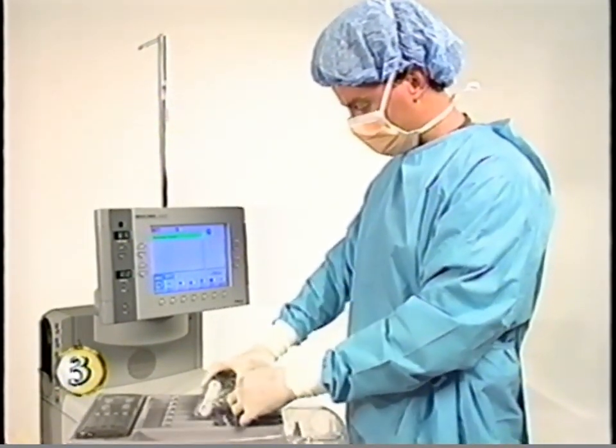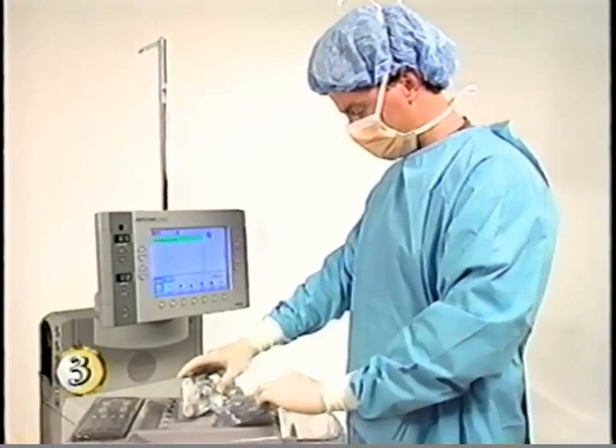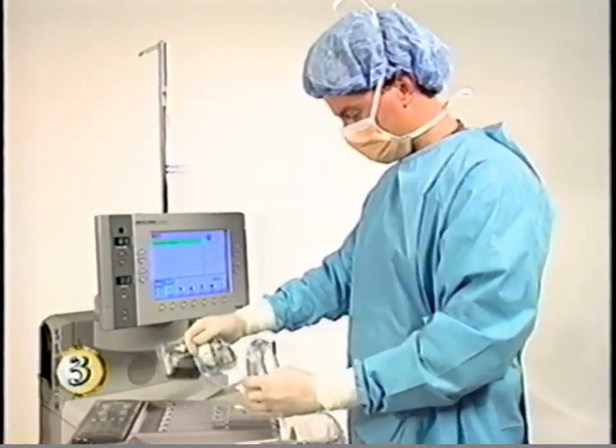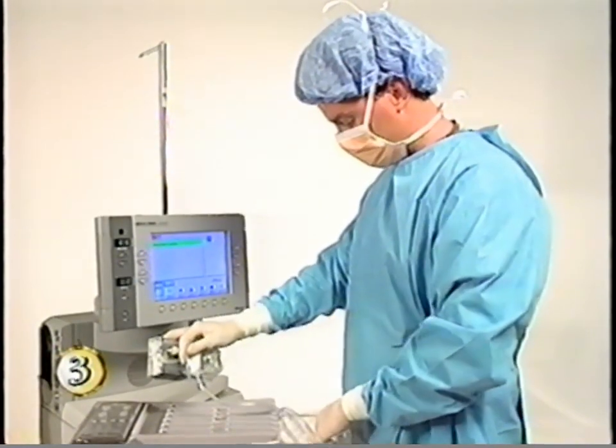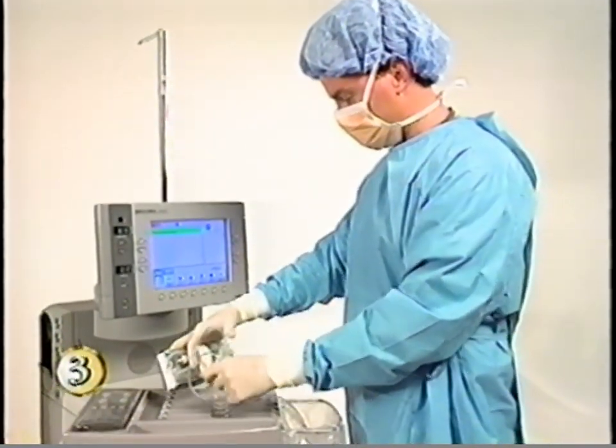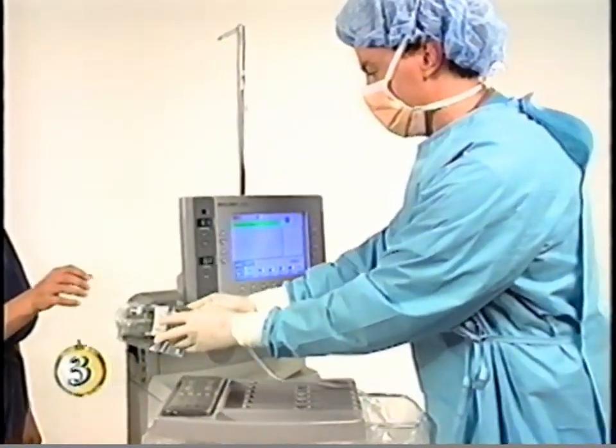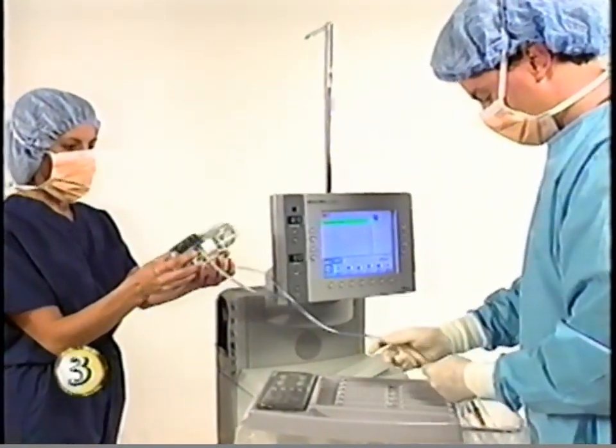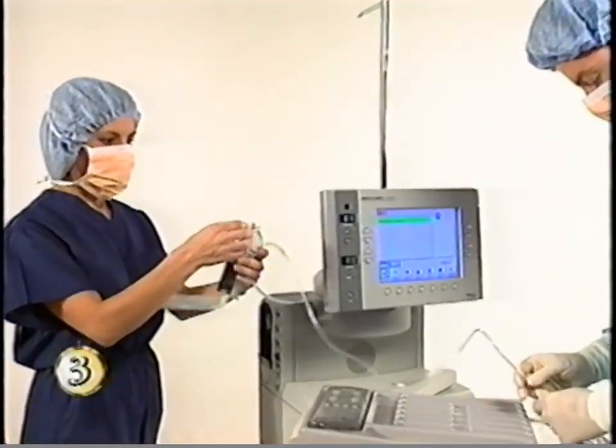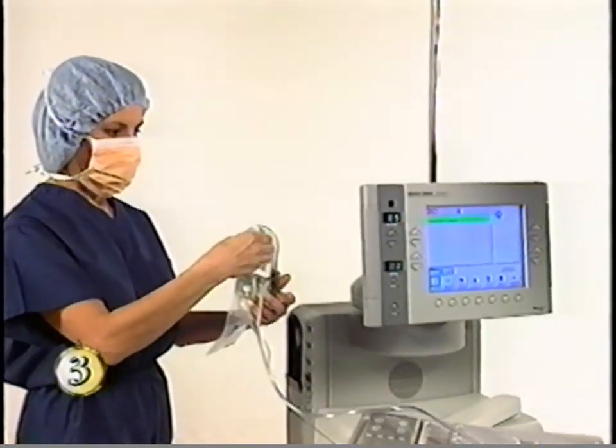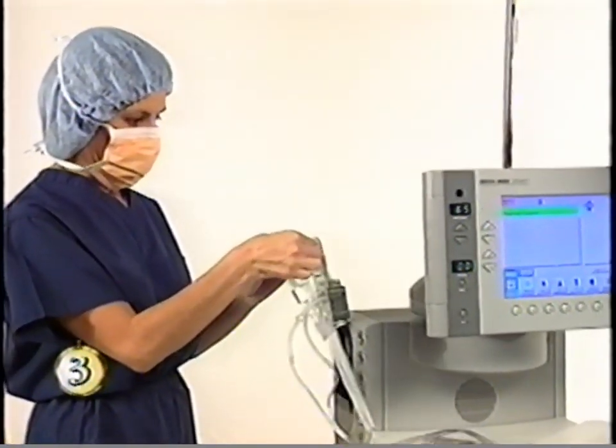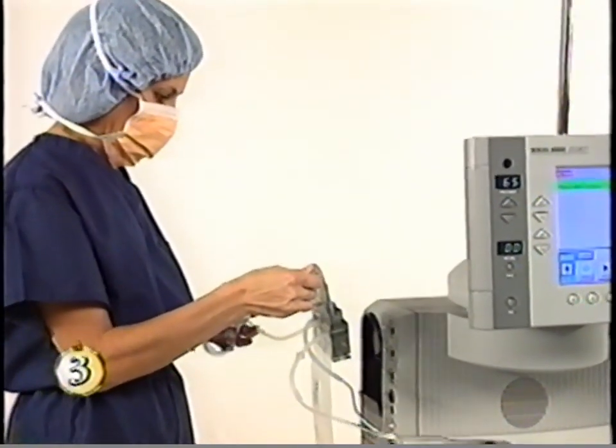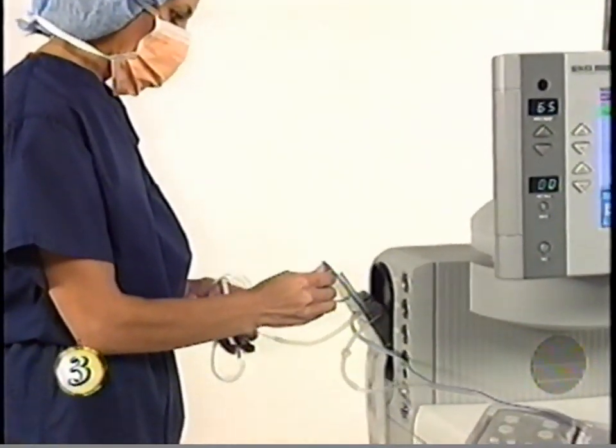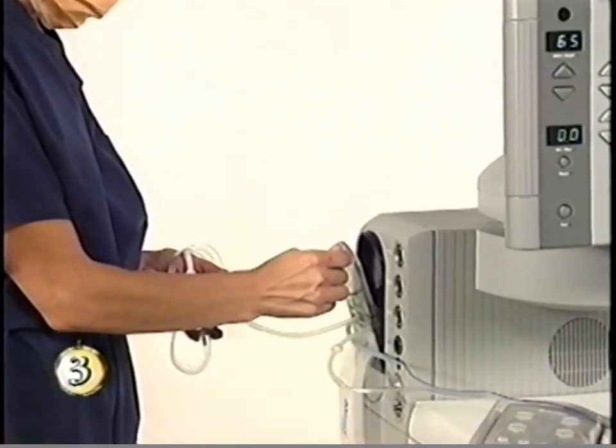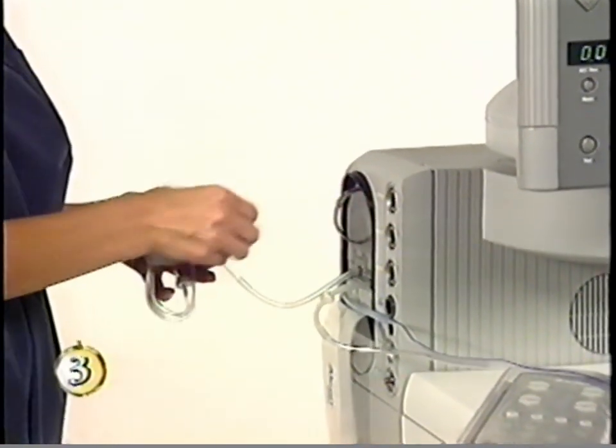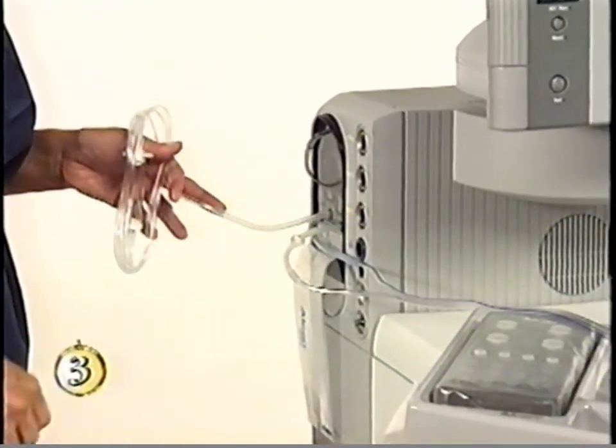The scrub nurse breaks the paper band on the irrigation and aspiration tubing and uncoils the top portion, placing it into the tray cover pouch. The scrub nurse passes the cassette and irrigation line with drip chamber to the circulator. The cassette is held by its handle with the printing on the drainage bag facing out. The circulator inserts the cassette into its housing on the unit's left side. For proper fit, it is angled out and smoothly pressed down and into the housing.